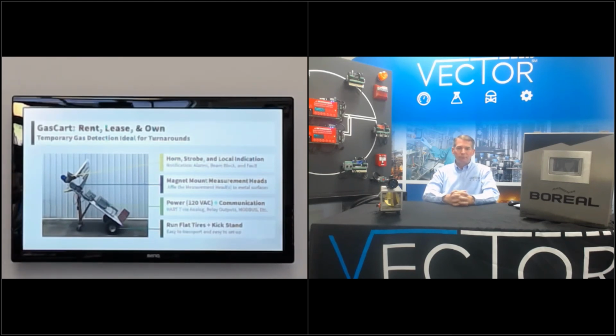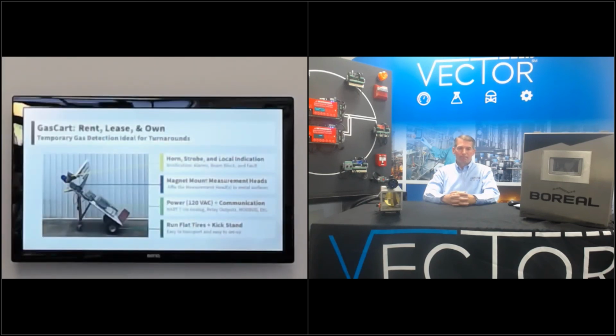Yeah, absolutely. Just as Chad mentioned, for turnarounds, in addition to purchasing this equipment, we do have ideal turnaround pieces of gas detection equipment that easily roll out into the field. That has explosion-proof plugs. You plug it directly into explosion-proof fittings or cheater cords. It tilts back for easy, stable alignment. And then the measurement heads come with 100-pound magnets attached to them. They just affix it to a stainless steel I-beam or anything else like that. And in addition to local indication on the touchscreen, you do have a horn and strobe arrangement for a complete standalone detection there as well.